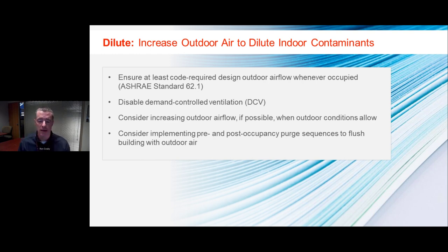So diving back to dilution though, you really want to mitigate the potential risk. To do that, you move to where at least you use the ASHRAE 62.1 design minimum for outdoor airflow into the spaces that are occupied. In pandemic mode, so maybe in a critical pandemic mode, you want to disable demand control ventilation. That way ventilation is on as much as possible, so you get as much outside air as possible. So you're always trying to pull in more outside air with this dilution mitigation.